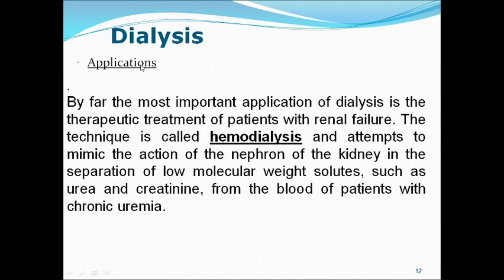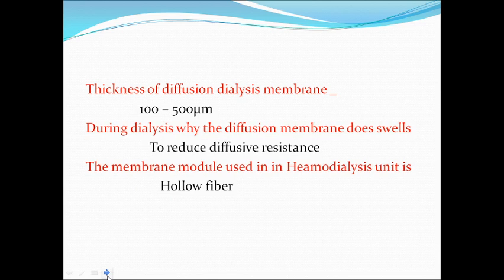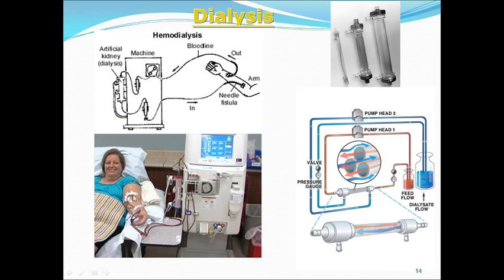Application: if you use a membrane to purify blood, that is referred to as hemodialysis. It is a technique and therapy treatment of patients with renal failure that attempts to mimic the action of the nephron of the kidney — the separation of low molecular weight solutes such as urea and creatinine from the blood of patients with chronic uremia. The thickness of the diffusion dialysis membrane is usually in the range of 100 to 500 micrometers. During dialysis, the diffusion membrane swells to reduce diffusive resistance. The membrane module used in the hemodialysis unit is referred to as hollow fiber.